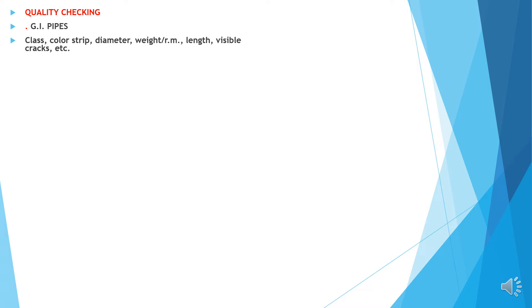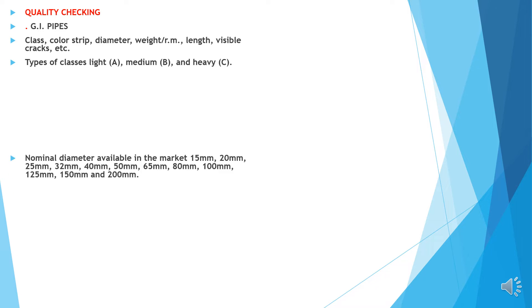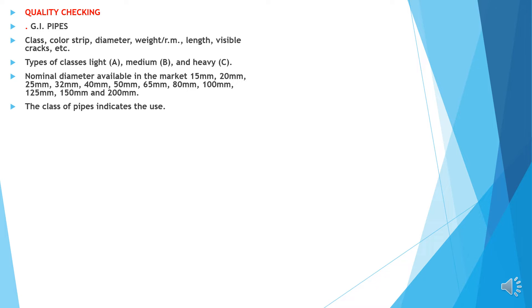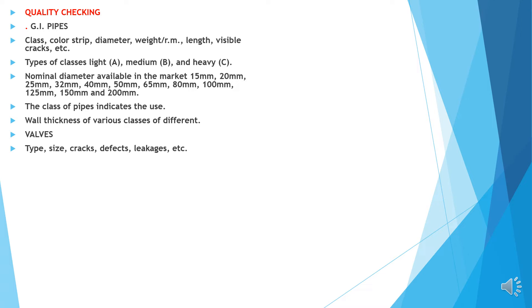Quality checking. G.I. pipes: check class, colors, stripe, diameter, weight, length, visible cracks, etc. Types of classes: light, medium and heavy. Nominal diameter available in market: 15 to 200 mm. The class of pipe indicates the use; wall thickness of various classes are different. Valves: check type, sizes, cracks, defects, leakages, etc. CP fittings: check type, surface finish, leakages, threading, etc.